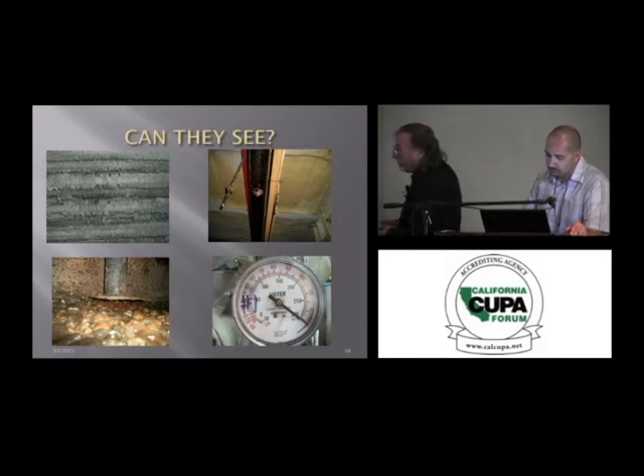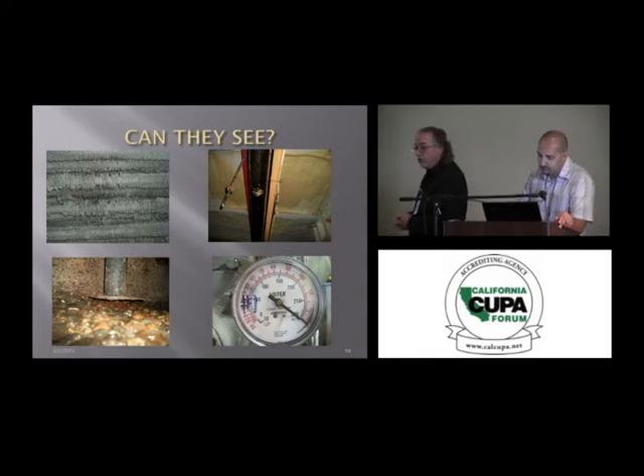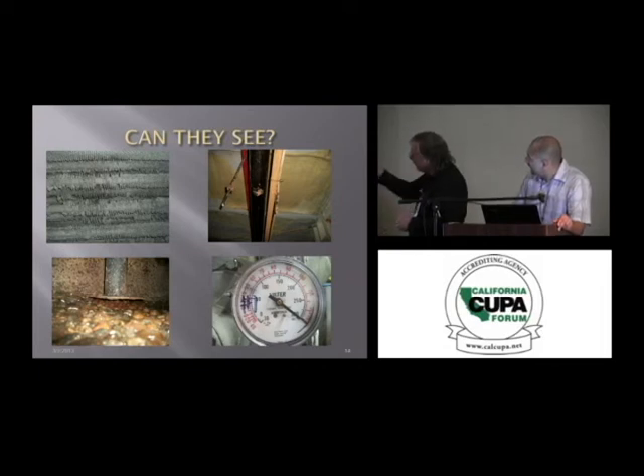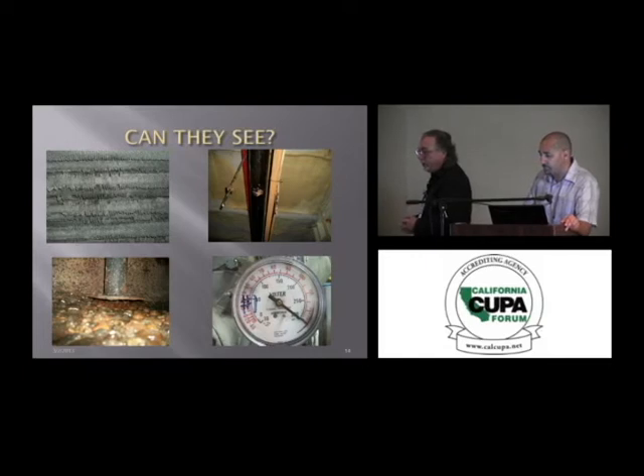When you get into banana rooms, where we have banana ripening rooms, then they're using ethylene. All those things cause corrosion to the air units, and so they have to inspect those on a regular basis. A lot of people think that these coils are going to be good for 25 to 40 years. In those corrosive atmospheres, they won't last that long. So they need a little more attention than, say, a cold storage warehouse or something that doesn't use those chemicals.